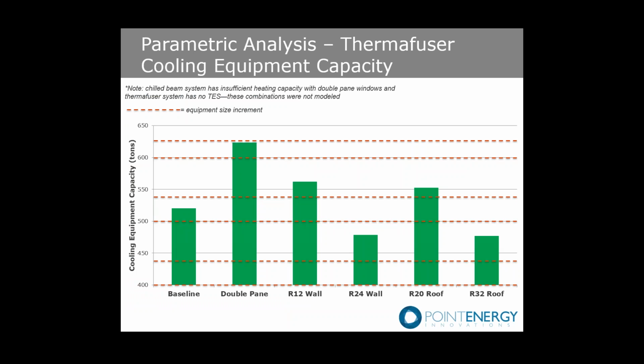In this case, we looked at several design options in terms of wall insulation and window type, and what that does to our cooling equipment capacity. Cooling equipment doesn't come in 1-ton increments from 0 to 1,000 tons. You have buckets, and once you get above a certain point you may need to buy a much larger piece of equipment.